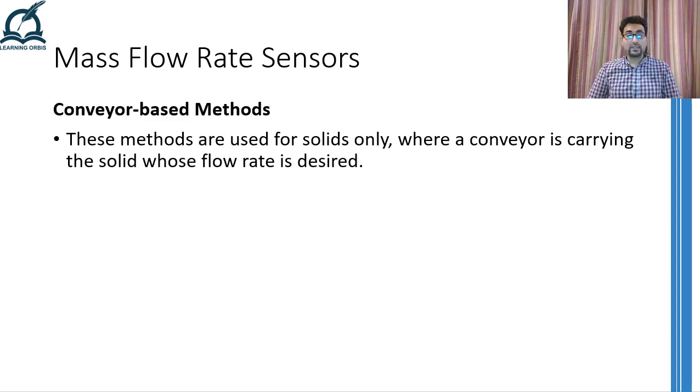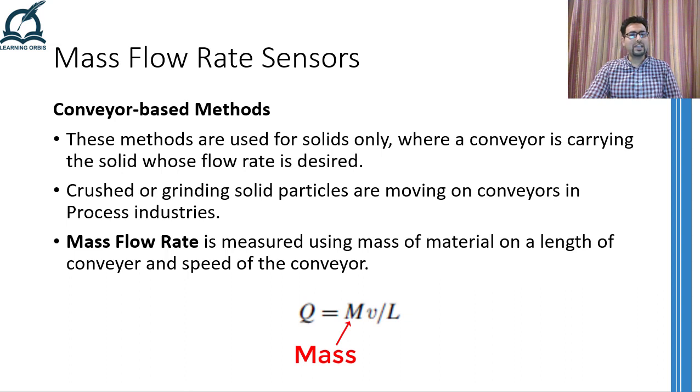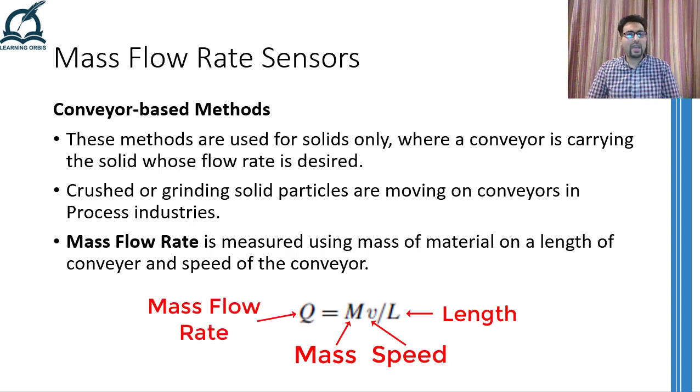The very first method is in fact a combination of methods in which solid particles are traveling on an open conveyor. Therefore, these methods are combined under the heading of conveyor-based methods. The working principle of these methods is very straightforward. That is, we measure the weight of the section of a conveyor on which some grinded or crushed solid particles are traveling. Convert that weight into mass and multiply it with the speed of the conveyor. And lastly, divide it by the length of this section which we were considering will give us the mass flow rate.